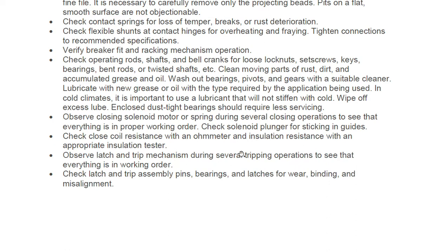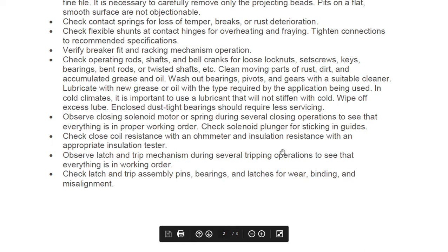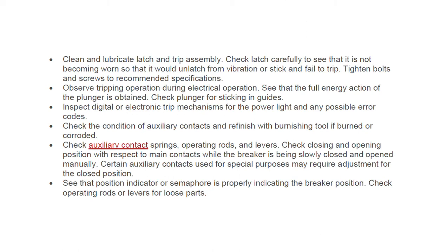So there is a latch and trip mechanism that we are supposed to see during several tripping operations to see that everything is in working order. Check latch and trip assembly pins, bearings and latches for wear, binding and misalignment. So that is also important. Clean and lubricate latch and trip. So that also we are supposed to observe tripping operation during electrical operation. So whether it is tripping or not, that we are supposed to see, because it is important. In an overload condition it is supposed to trip.